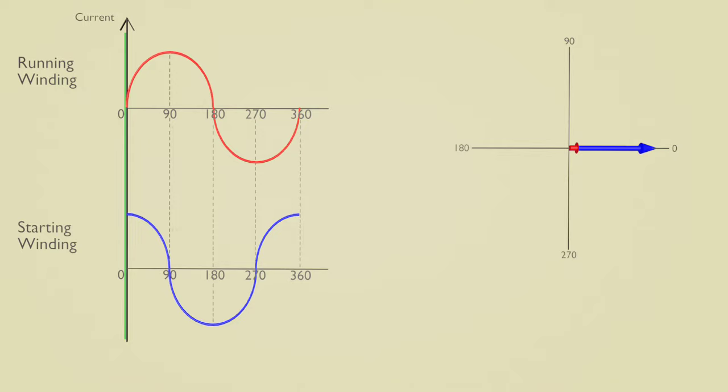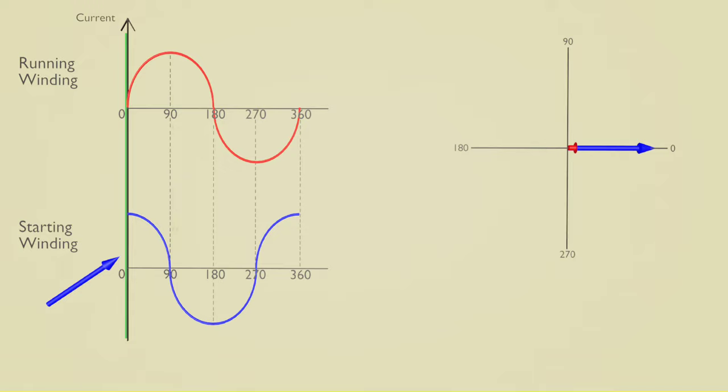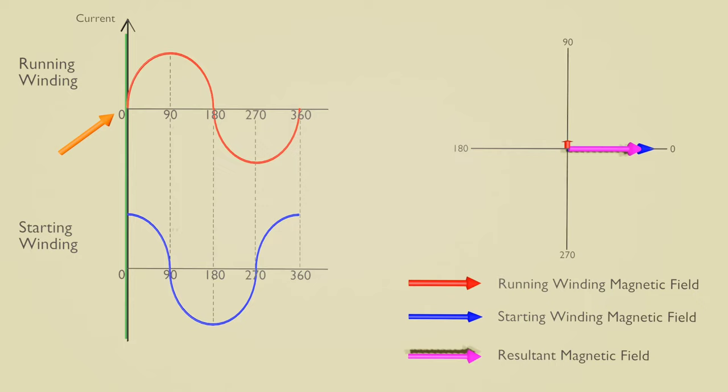There are two waveforms of current in starting winding and running winding. The capacitor is in series with starting winding, so the current in starting winding leads by 90 degrees. We know that the magnetic field or flux is directly proportional to the current, so the magnetic field of starting winding also leads by 90 degrees.